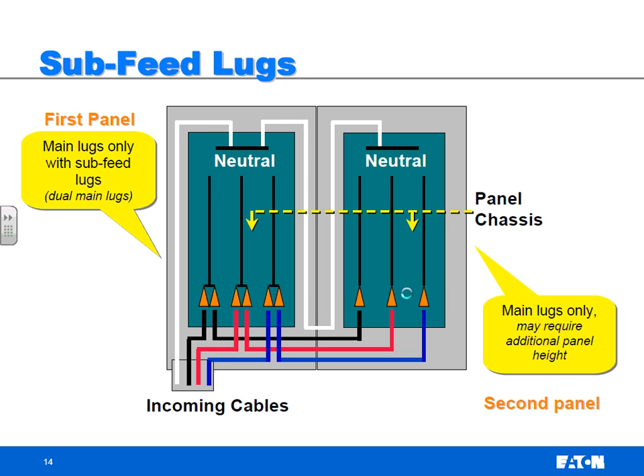It's common when you do this side-by-side panel to make both panels the same height. So this is going to have double lugs, this is going to have single lugs, and maybe you've got 42 circuits here and you only need 18 more circuits. Well, you could probably build this in 60 inches high and this one in 42 inches high. But aesthetically, it really isn't going to look that good. And if you're making this connection straight across the bottom, it's much easier to have those panelboards the same height. So a lot of times you'll make the second one taller just so it looks like a big square or rectangle versus kind of offset equipment.